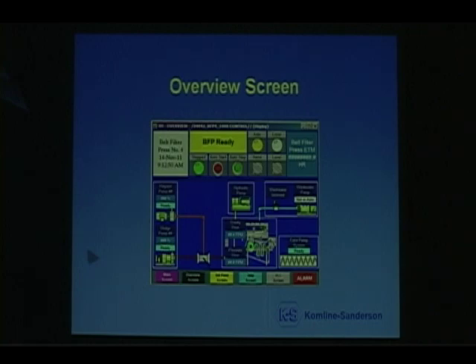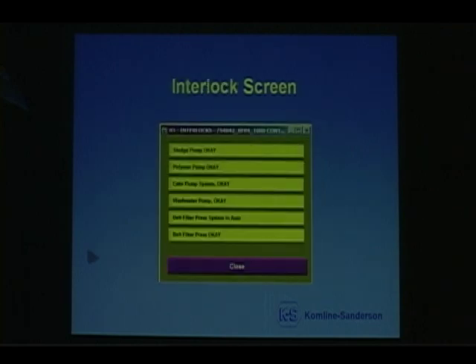The BFP ready screen, if you touch that, what they call the interlock screen will pop up for automatic mode. This screen will appear. If one of those is not okay and the press is not in auto, it will say interlocks not met, and it'll tell you which one of those is not okay. You can go to the SCADA screen, make it okay, and then the press will be able to operate in auto.